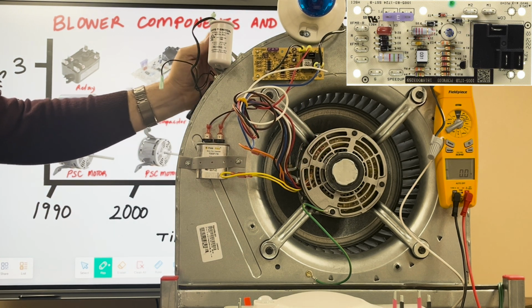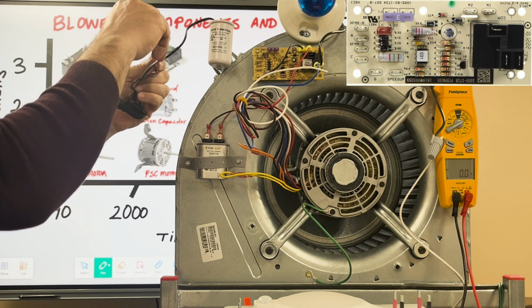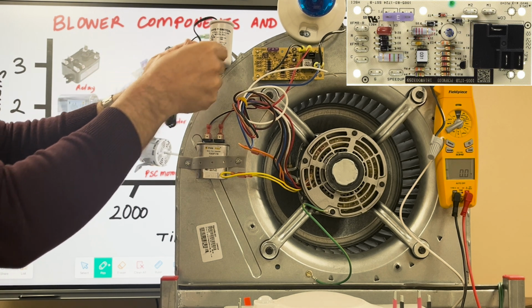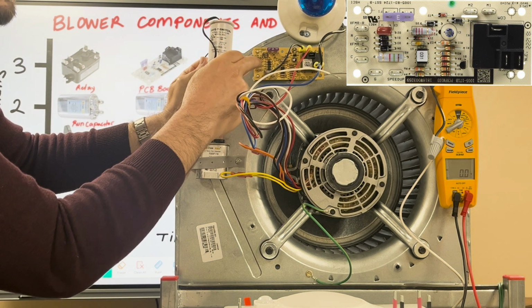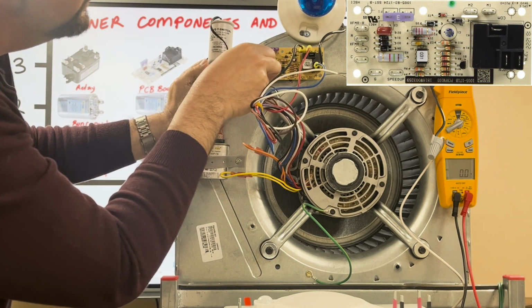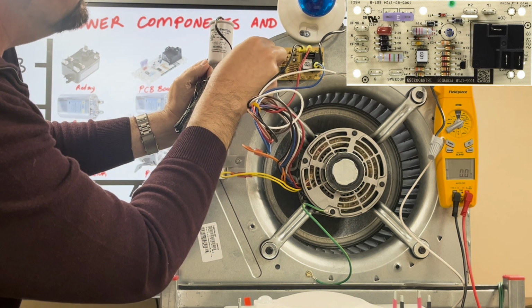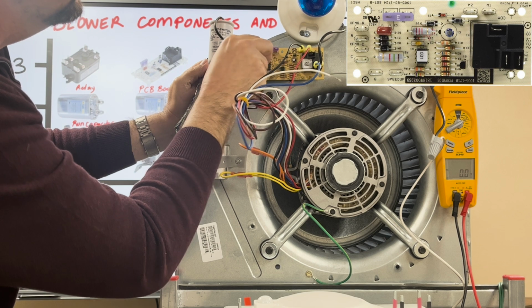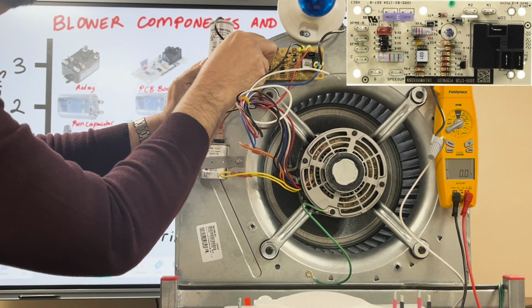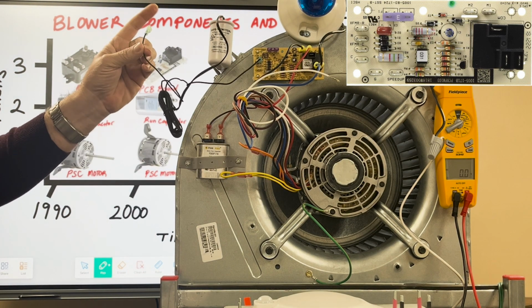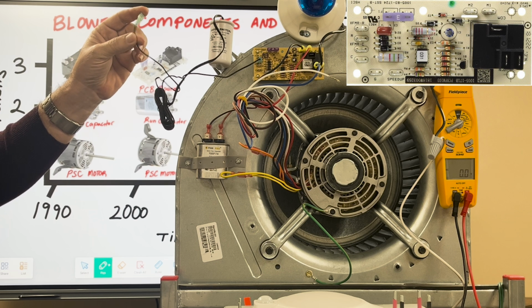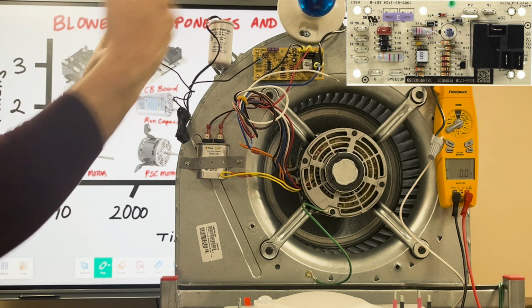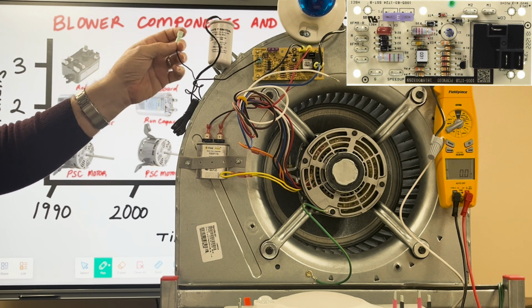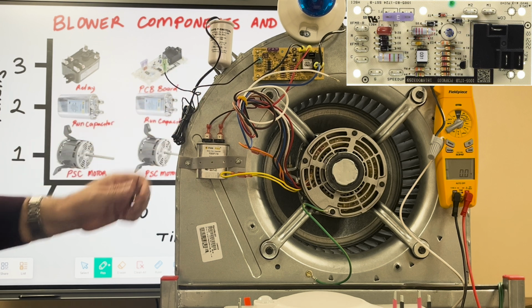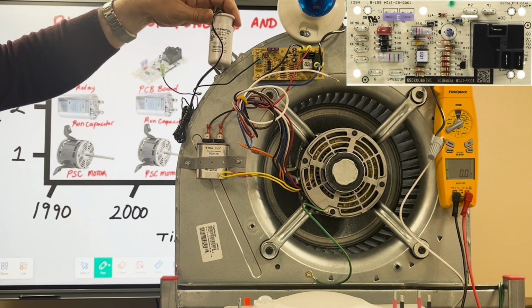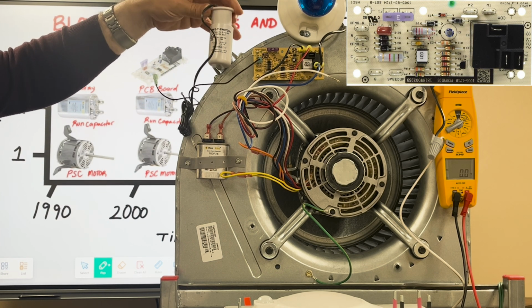So I'm going to wire my float switch to the second terminal down on the top left, okay? That will just say R, and that's an R output. Theoretically, I would wire this other side of my float switch to whatever's going to my thermostat, so I can break power to my T-stat in the event my float switch tripped.